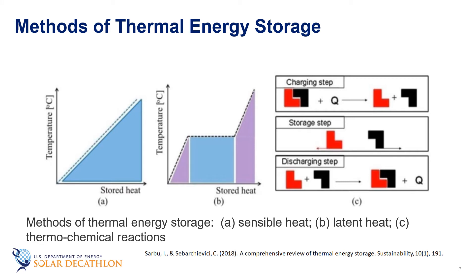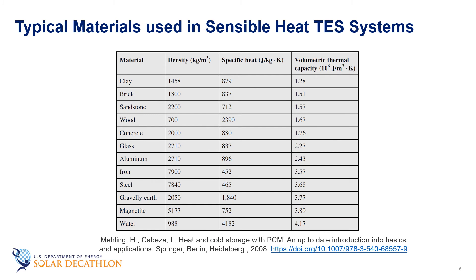There are three methods for thermal energy storage at temperatures ranging from minus 40 degrees Celsius to more than 400 degrees Celsius. Those are sensible heat, latent heat, and thermochemical heat storage associated with chemical reactions. The choice of the storage medium depends on the nature of the process — for example, for water heating, energy storage as sensible heat of stored water is logical. Sensible heat storage is the simplest thermal energy storage method, involving heating or cooling of a liquid or solid storage medium.